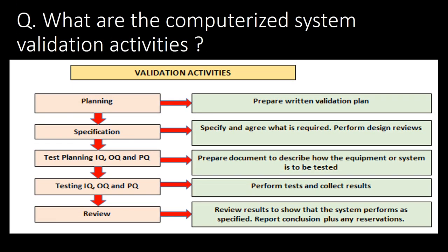What are the computerized system validation activities? There are five major activities. First, planning, where a written validation plan is prepared. Second, specification, where we specify and agree on what is required and perform design reviews. Third, test planning for IQ, OQ, and PQ, where we prepare documents to describe how the equipment or system is to be tested. Fourth, testing IQ, OQ, and PQ, where we perform tests and collect results. Fifth, review, where we review results to show that the system performs as specified and report conclusions plus any reservations.